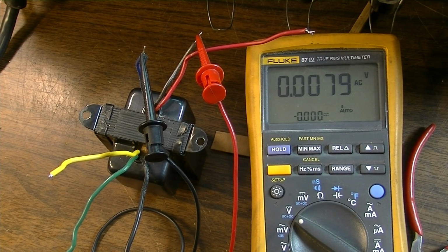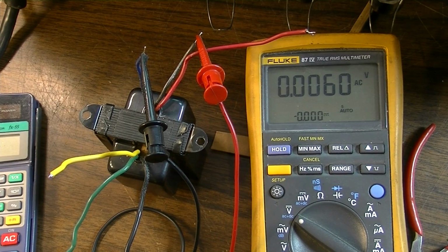So what we can do now is calculate what the primary impedance is going to be based on the secondary impedances. If we assume we're using our 8 ohm tap, which on this side we measured, we could have measured our 4 ohm tap as well and done the calculations that way, and we would have arrived at the same conclusions — just with the 4 ohm tap.